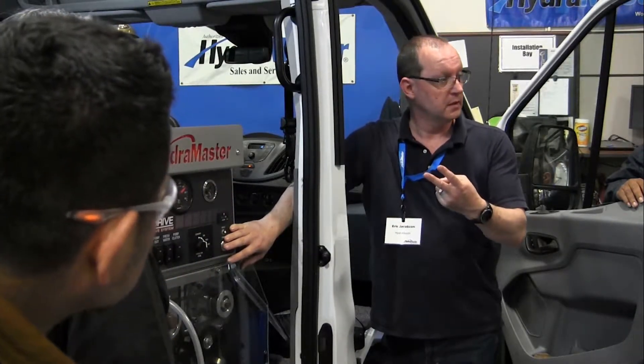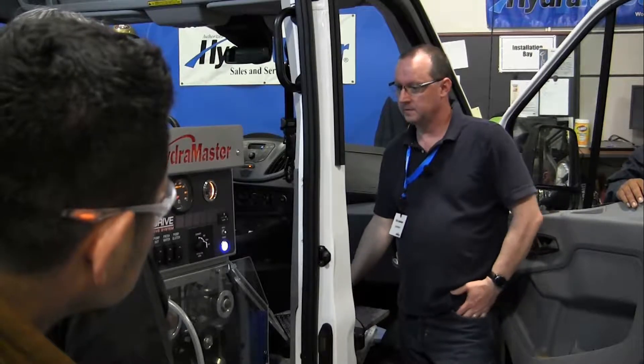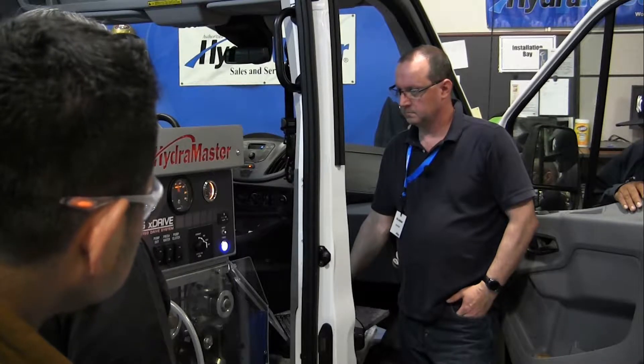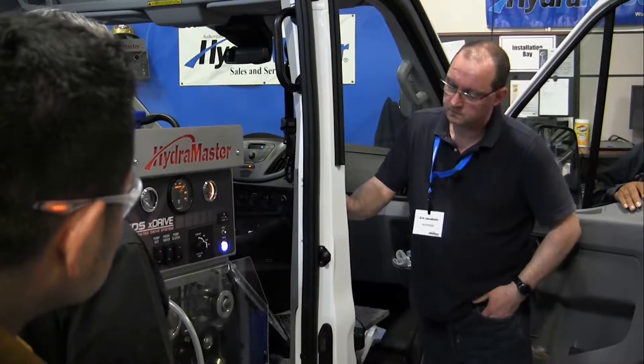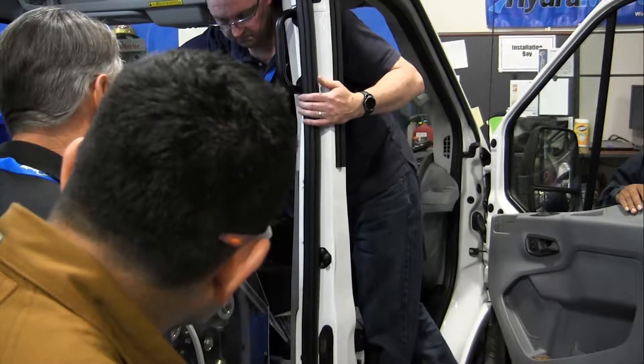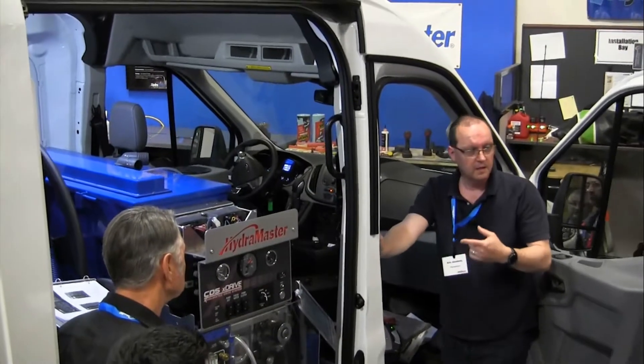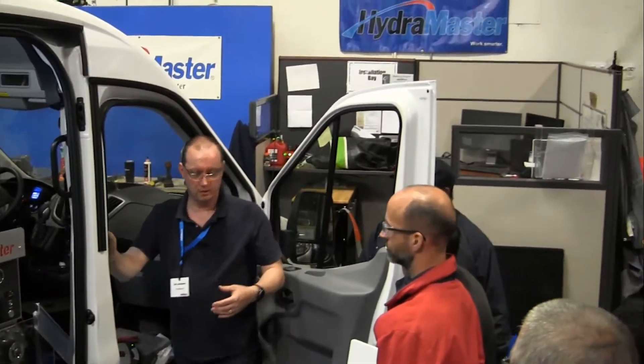I just dropped out one of the contactors, so this is how it runs on two phases if one of those contactors goes out. At economy, it's virtually undetectable because you're really not requiring that much power from it.